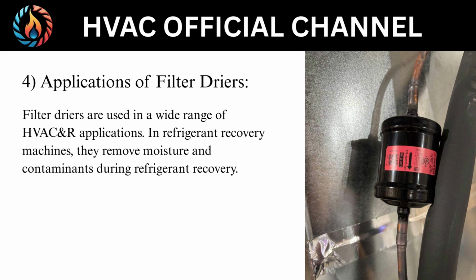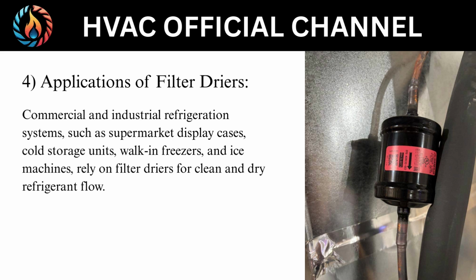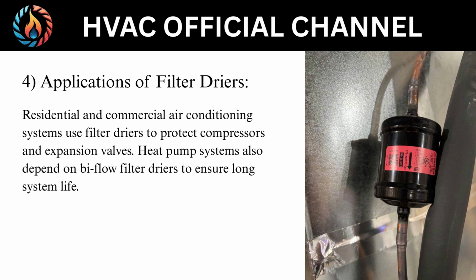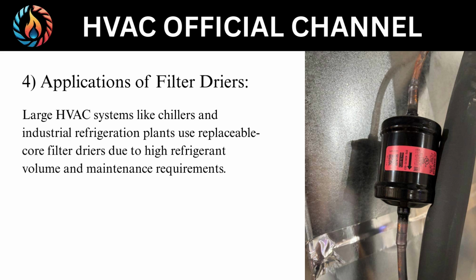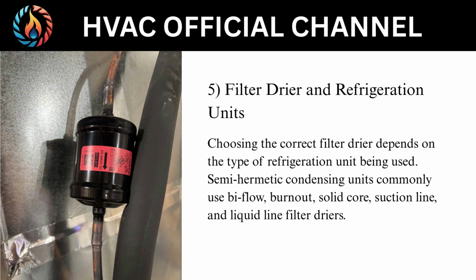Filter dryers are used in a wide range of HVAC&R applications. In refrigerant recovery machines, they remove moisture and contaminants during refrigerant recovery. Commercial and industrial refrigeration systems, such as supermarket display cases, cold storage units, walk-in freezers, and ice machines, rely on filter dryers for clean and dry refrigerant flow. Residential and commercial air conditioning systems use filter dryers to protect compressors and expansion valves. Heat pump systems also depend on biflow filter dryers to ensure long system life. Large HVAC systems like chillers and industrial refrigeration plants use replaceable core filter dryers due to high refrigerant volume and maintenance requirements. 5. Filter dryer and refrigeration units.